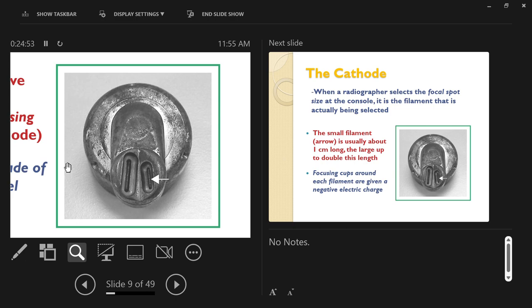With a dual focus tube, you can use one filament or the other. There are good reasons for this: the larger filament can handle more electrons moving through it, so for a bigger exposure where you want to make more x-rays, the larger filament is better. The small filament allows you to run fewer electrons through it.